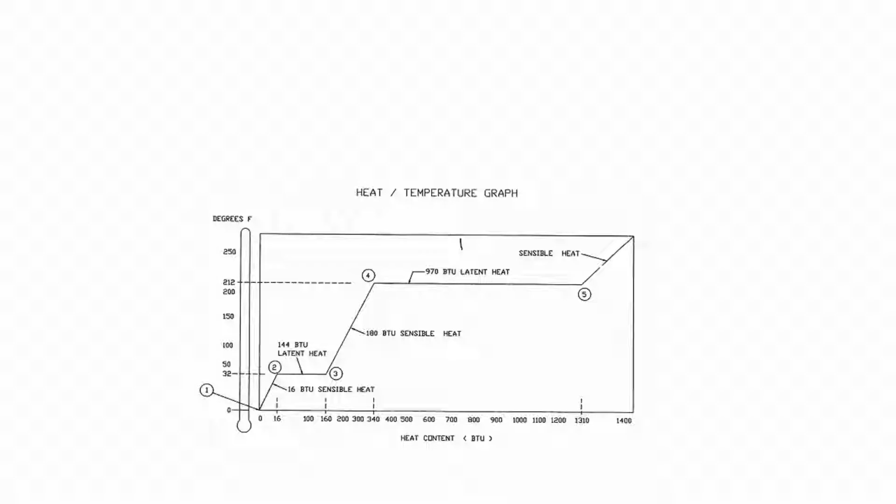When adding or removing heat and there is a change in temperature, but no change in state, it is called sensible heat. When adding or removing heat and there is no change in temperature, but there is a change in state of the substance, it is called latent heat.